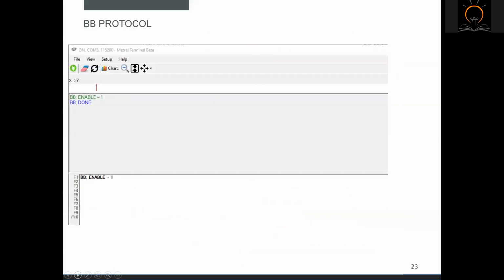For testing or presentation purposes, Metrel uses terminal software. Now I will show how the execution of one of the use cases presented in the document can be performed using the Metrel terminal software. Sending the string bb enable equals 1 puts the instrument into black box mode. The instrument returns an answer, BB: DONE.